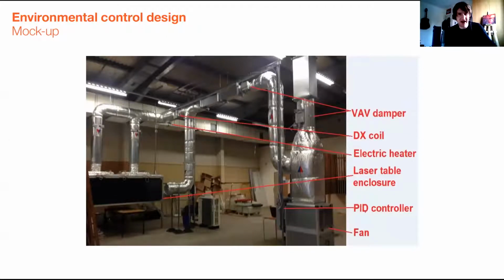So we did this in a warehouse. This is a photo of the mock-up that we built. It was built in a warehouse nearby that was client provided. And the client also provided the actual laser table enclosure that you can see there on the left, which was the same specification that was going to be provided on the project. And essentially what we wanted to test was the strategy I just explained: if we wash that environmental box with air at a very stable condition, will we maintain that very stable condition in the box itself? So we built this mock-up.